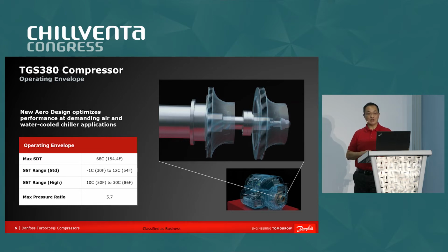It can also be utilized in high temperature cooling applications, such that it can achieve high saturated suction temperatures up to 30 C. So this makes it very useful for applications like data center cooling, which typically requires high temperature water for cooling. And then also it can be utilized for just standard comfort cooling conditions, where you may want to use 12 C saturated suction temperature for comfort cooling applications.